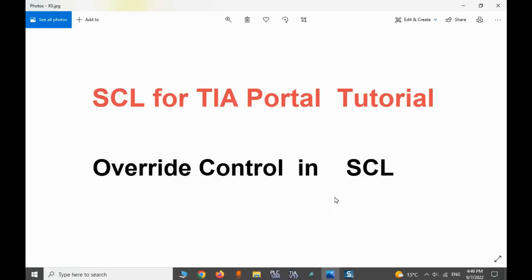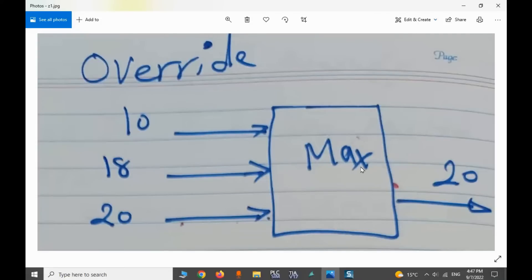We are back with the override control in SCL. For override control, we may have several values — some of them can be outputs of PID controllers, and some of them will be constants like the minimum opening of a valve. Three or four values will enter a selector — this can be a selector block, override block, or min-max block — and based on the values, we choose the proper output.